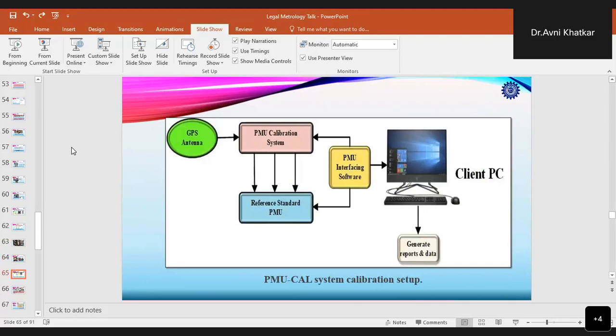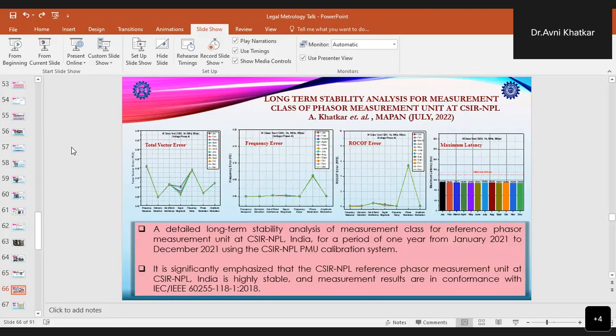This is the setup of the PMU calibration system. In this way, we generate all the reports and data using the PMU calibration system. All the inputs are time stamped to GPS. These are the results of long-term stability and analysis of measurement class of PMUs, which was done at NPL. These results were carried out for a period of 1 year, from January 21 to December 21, using the CSIR NPL's PMU calibration system. These results significantly emphasize that the CSIR NPL's reference PMU is very stable, and all the measurement results are in conformance with the IEEE standard.